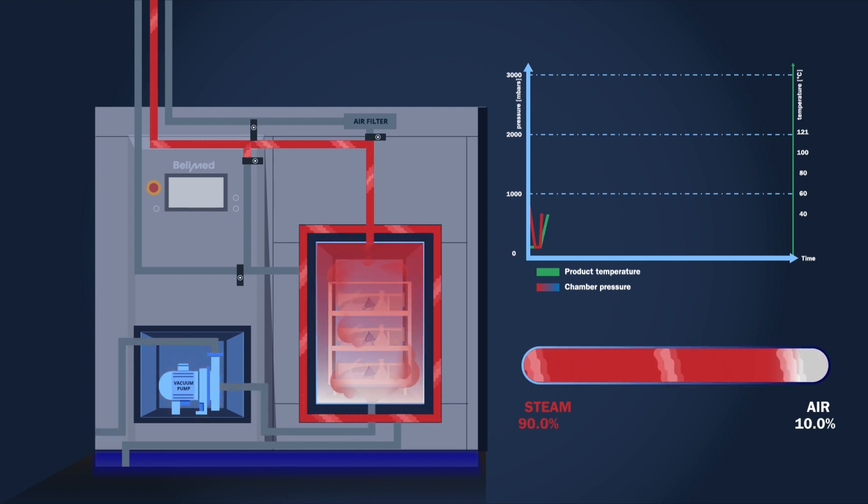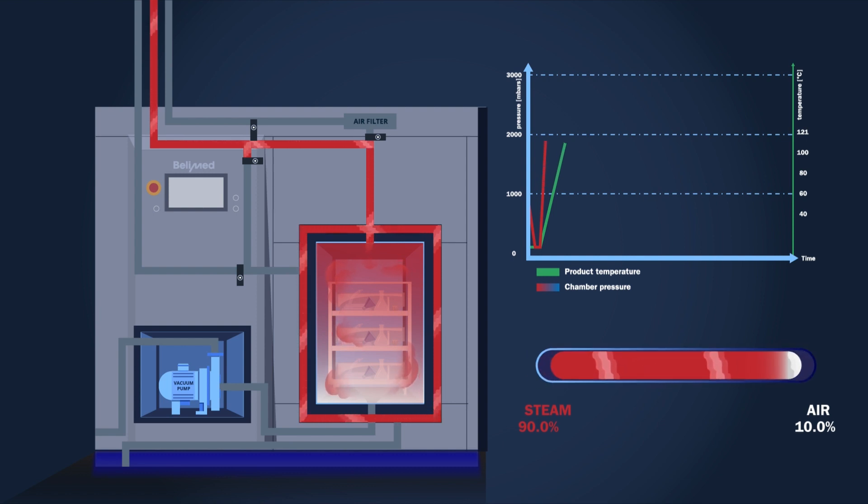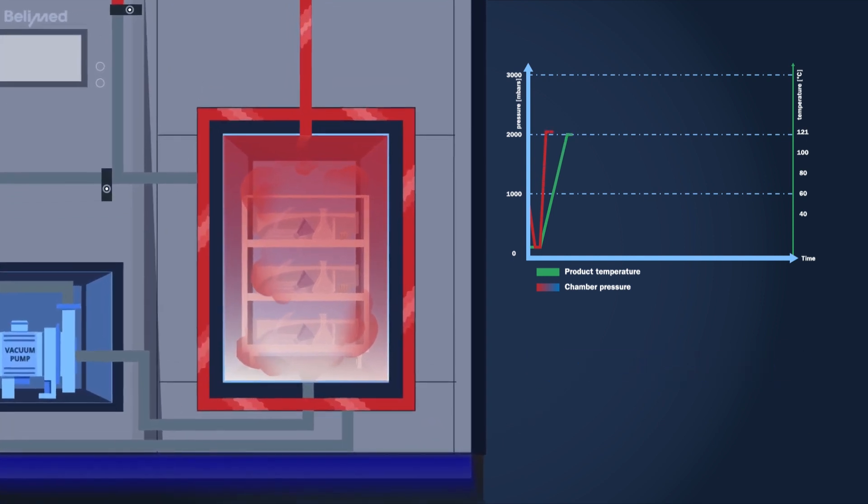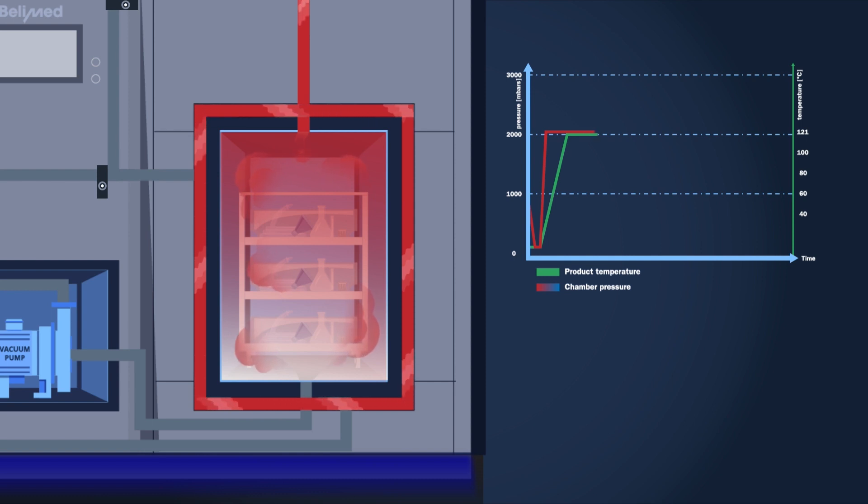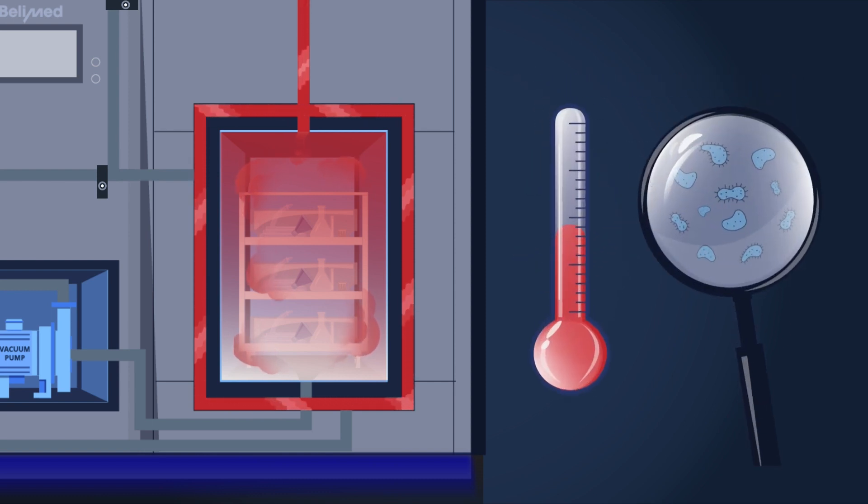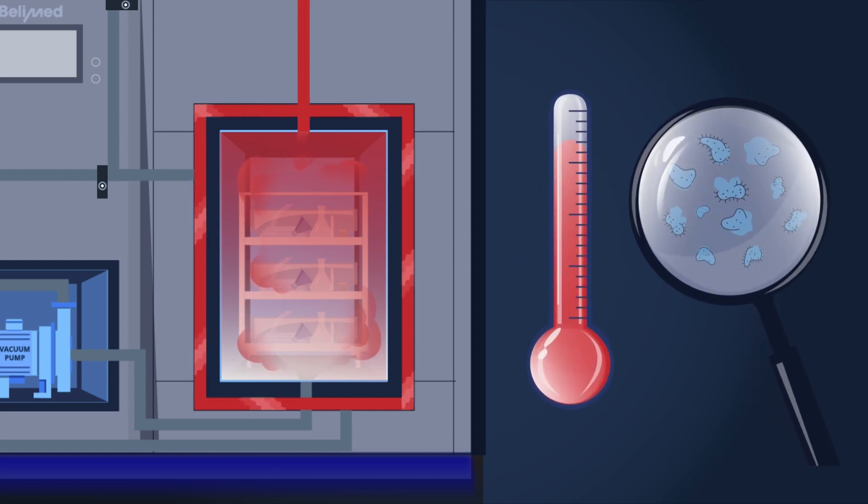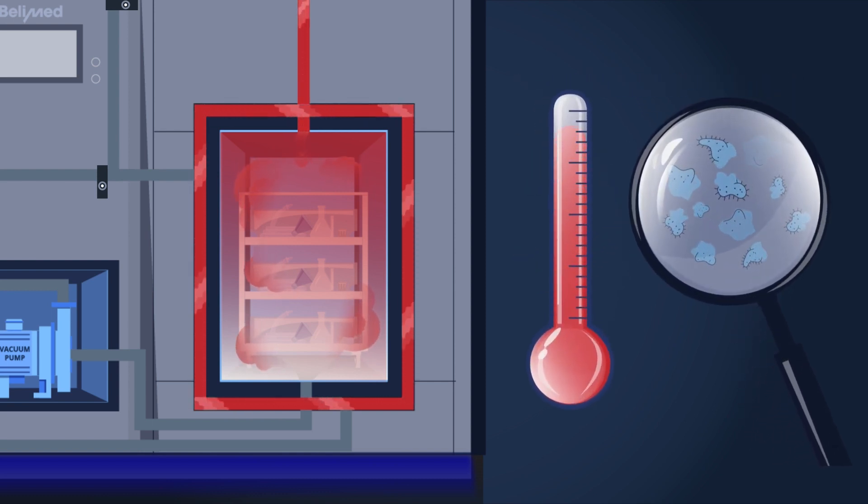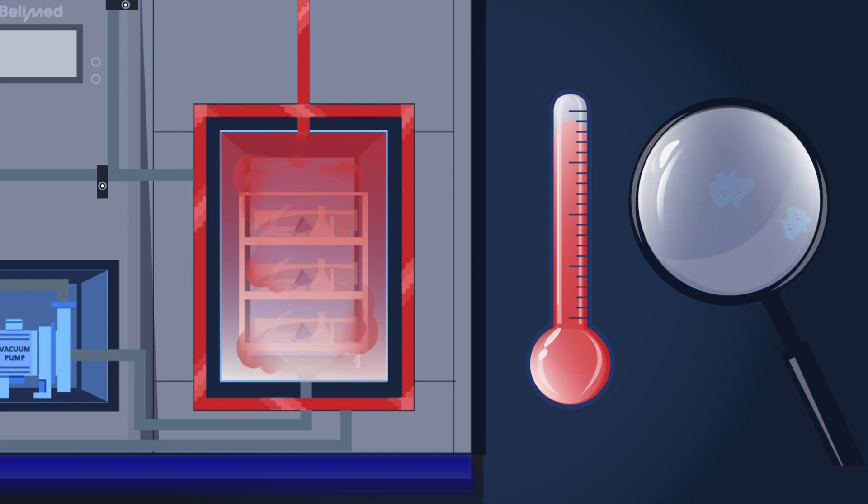Then, steam is filled in the chamber till a set temperature has been reached. Hot steam heats up all products to the set sterilizing temperature, so all microorganisms are killed by the heat. Depending on the product to be sterilized, the duration of this phase can be adapted.